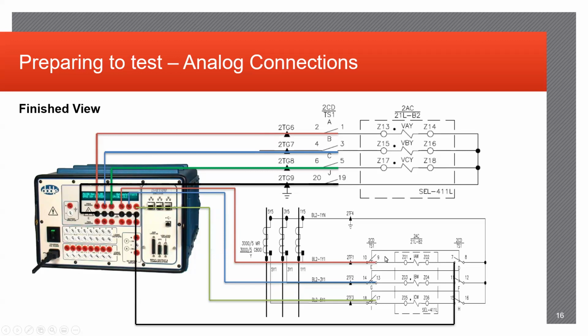You need to verify that the relay is going to be receiving the correct current values. So in this case, you'll have your phase A coming in, and you need to jump. Usually, once these are isolated, you'll need to jump 7, 11, and 15 altogether to get your reference back. Otherwise, it's an open CT, and the test set won't even allow you to inject any current.